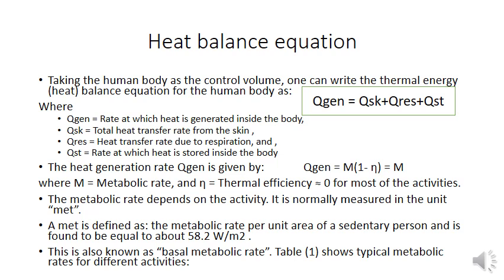Q_gen can also be expressed in terms of metabolic rate: Q_gen = M × (1 − η), where M is the metabolic rate and η is the thermal efficiency — which is mostly zero for maximum day-to-day routine activities, so Q_gen equals the metabolic rate. The metabolic rate depends on activity and is measured in the unit 'met'. One met is defined as the metabolic rate per unit area, equal to 58.2 W/m², also known as the basal metabolic rate.